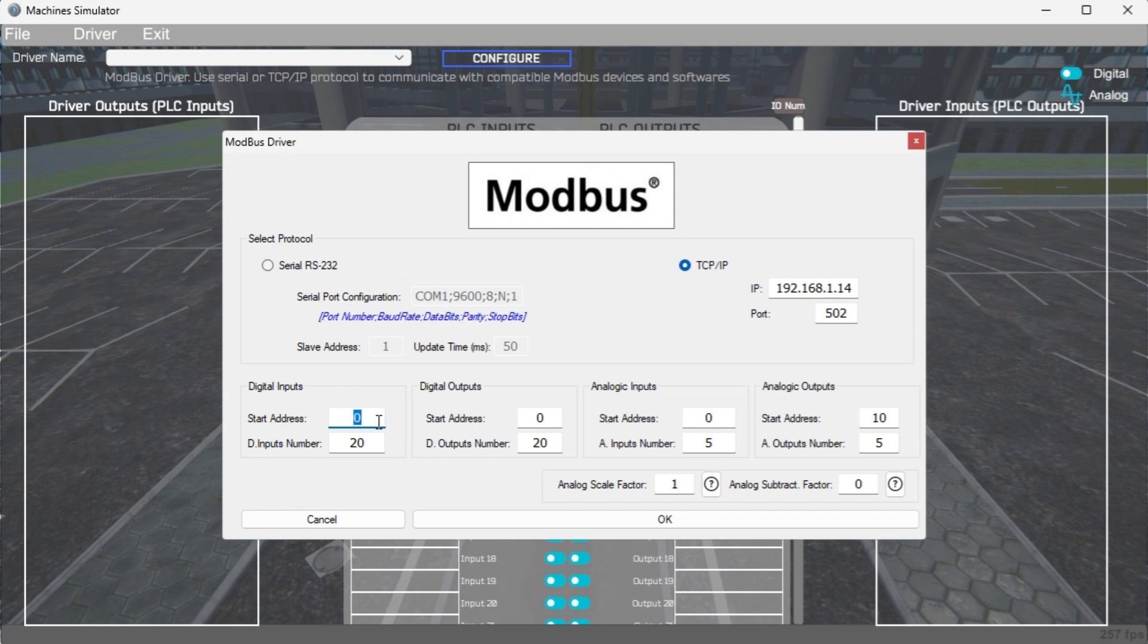The digital inputs from MS to the Do More PLC will start at 1-00001. This will begin at address 0 due to the offset of 1. Digital outputs from MS to the Do More PLC will start at 1. This will begin at address 0 again due to the offset of 1.